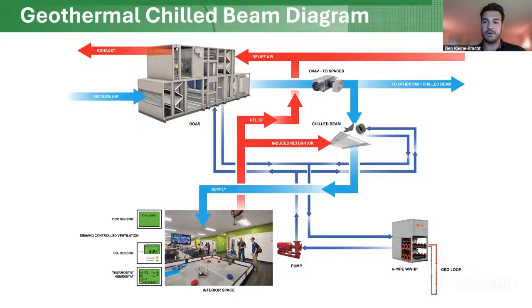I wanted to highlight these lower EUI options, knowing the goals of this project. So we have a 6-pipe unit here, like I said, this would live in the mechanical room. 6 pipes, it's got all the compressors in it, modular. You could probably have 5 or 6 of these stacked up in the walls - it wouldn't be this small, a little bit bigger, but this would provide all the heating and cooling for the entire building. You'd have 2 of these pumps, a chilled water pump and a hot water pump, distributing water to the DOAS and the chilled beams. Then the air comes from the air handling unit into the top of the chilled beams and either gets heated or cooled to set point.